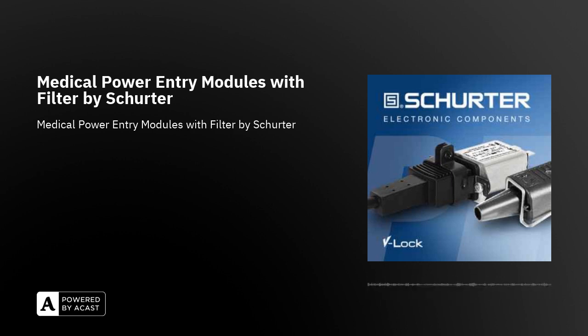The requirement for fuse holders is that energized supply leads have to be protected by a fuse to minimize the risk that if a failure occurs, the main circuit breaker might be tripped, disconnecting other, maybe life-critical, devices. In some countries, the mains plug is not polarized. That means the power conductor could be on neutral line. For example, CEE plugs in Europe. The solution provided by Schurter is PEM with a 2-pole fuse holder that is recommended for all medical electrical equipment.